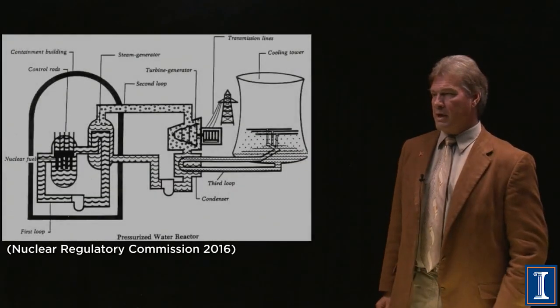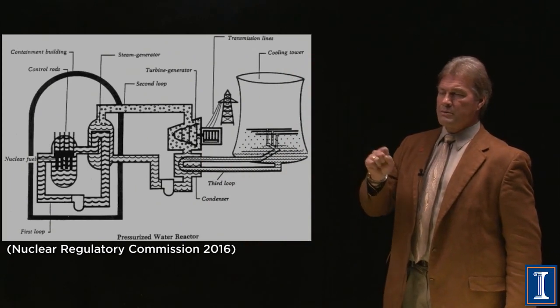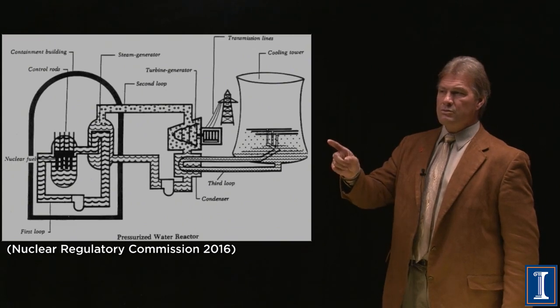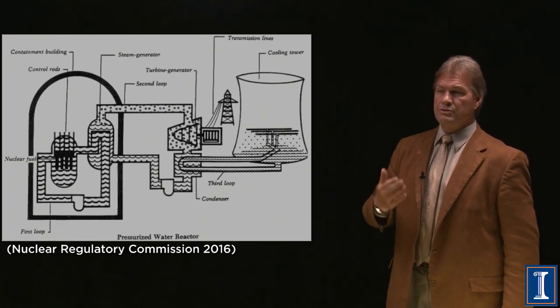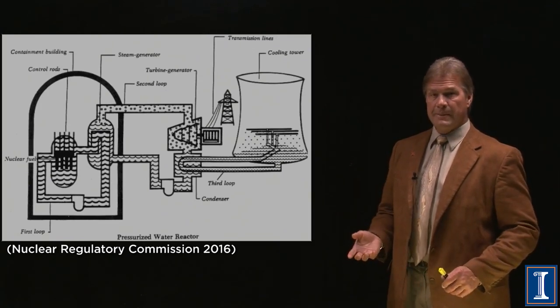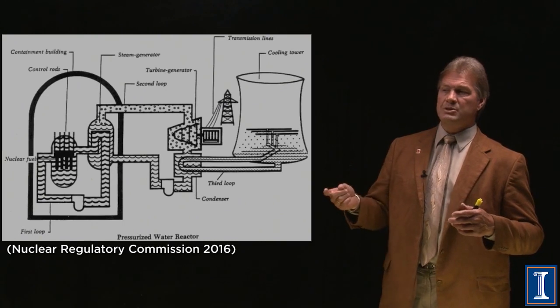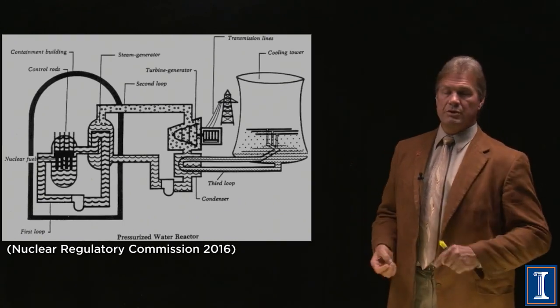So even though water is coming in and steam is going out, that's not a huge source of radioactivity. But initially, when people were worried about that, they made a different type of reactor — the pressurized water reactor. You'll notice there's another loop: the water that goes through the core goes into a heat exchanger, which turns a separate water supply into steam. That steam goes through the turbine, through the condenser, and circulates. You take a small efficiency hit from the extra loop, but you get a safety boost because the water that actually leaves the containment building never went through the core itself.